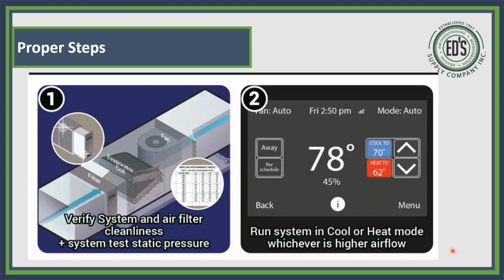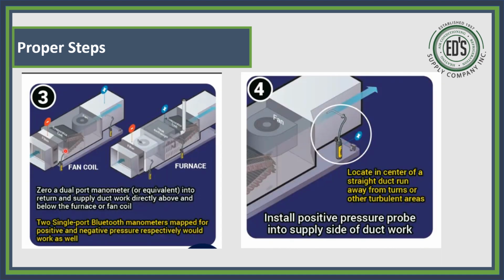So let's say we're going to put the pin in 3 or 5. We're going to test this in cool mode because the higher the fan speed, the higher the static pressure is going to be. Okay. So then we go on here to where we see this is a minus and this is a plus. We're going to put our manometer here and a manometer here. They're using the Fieldpiece Bluetooth dual port manometer for this. The first thing you need to do is zero it out. Once you've got your tubes hooked into your probes, you zero it out.